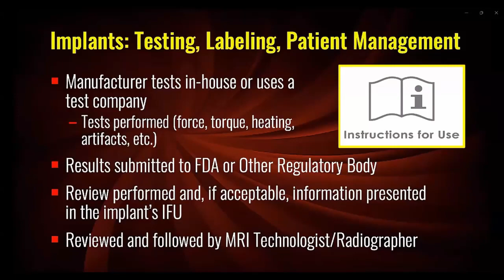When a patient with an implant presents for an MRI exam, the MRI technologist or radiographer obtains the information for the implant and carefully follows the labeling, which involves making sure that the relevant conditions are met to ensure patient safety. Be aware that in the vast majority of cases, the MRI testing and labeling typically only applies to 1.5 and or 3 Tesla scanners because these are the primary MRI systems used for clinical imaging worldwide. And to my knowledge, with the exception of a few cochlear implants, there are no implants that have been specifically tested and labeled below a field strength of 1.5 Tesla. As such, there is a general lack of labeling information for low field strength MR systems.